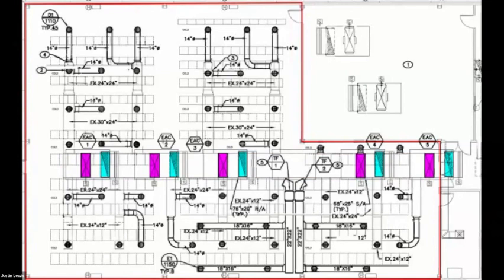So one interesting condition that we found when we started digging into the sequence and what was going on was that the units run 100% of the time. They never turn off. They run 24 hours a day. They ran at 100% speed in full cooling. And when they're satisfied, they drop down to 80% speed. There was no option for them to shut down in an occupied state. They would only shut down if their disconnect was turned off, they were put into service, or they had motorized dampers that would isolate. But this was not an automatic operation that was available for just a satisfied mode. This presented an interesting problem.